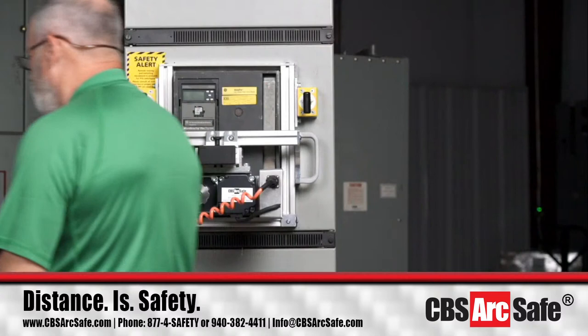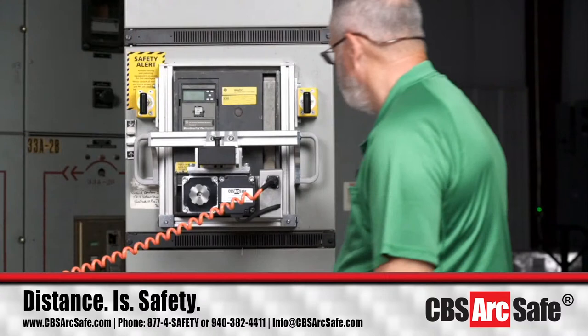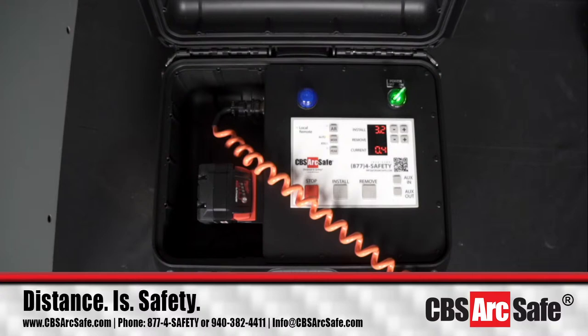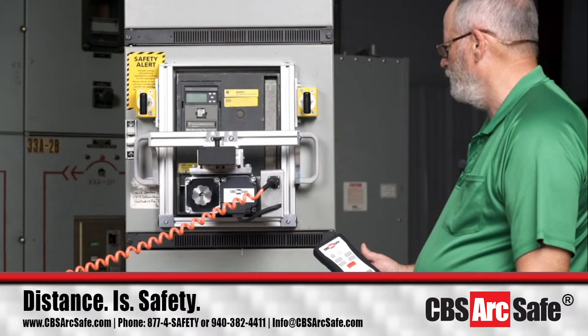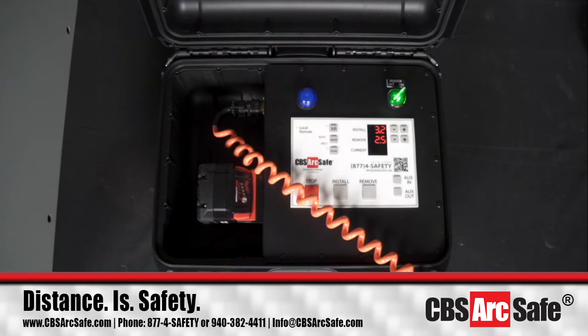Let me check something here. There we go. Now we're back. So now we're to install. And that's the installation process right there. What happened is when it came out, it got just past the end of the racking mechanism, so I just had to nudge it to get back to where it would start the racking process.